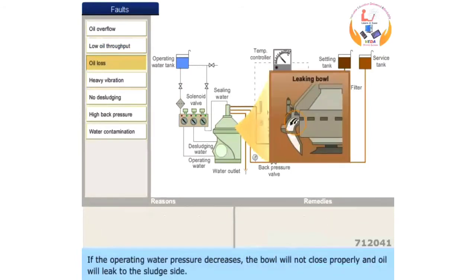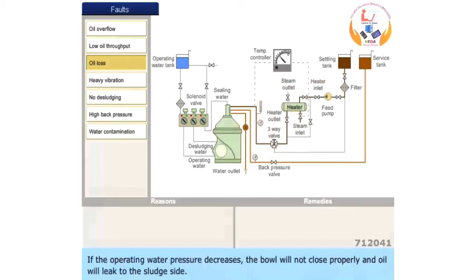If the operating water pressure decreases, the bowl will not close properly and oil will leak to the sludge side. The operating water pressure will reduce if the water line filter is clogged.